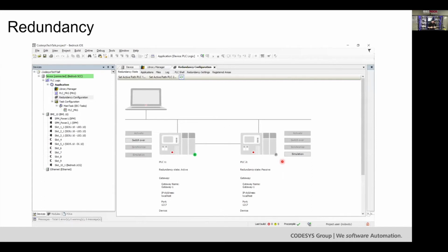What that ends up looking like is all you need to do in the software environment is add in a redundancy configuration. You set your path to the two controllers. Once this is downloaded with the redundancy configuration to your control system, this is going to cause the controllers to then synchronize, and now you're running in a full hot swappable redundant configuration.